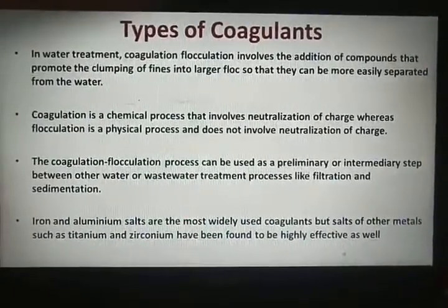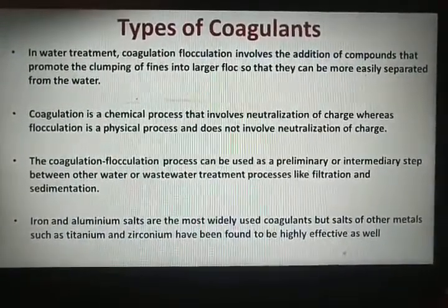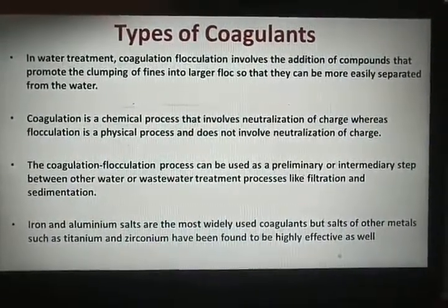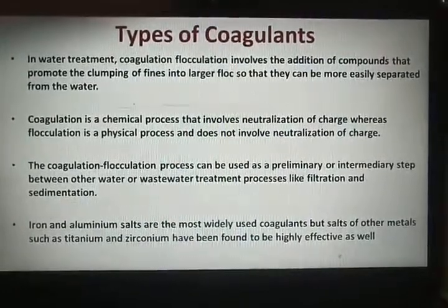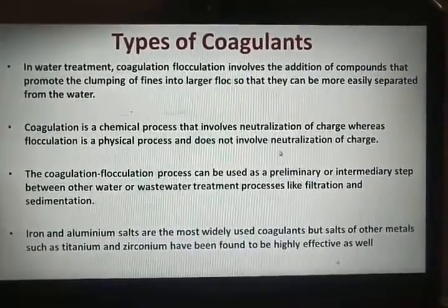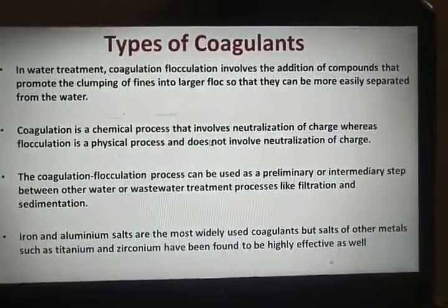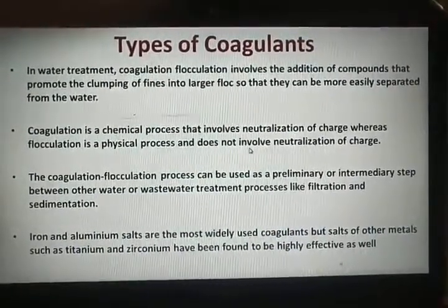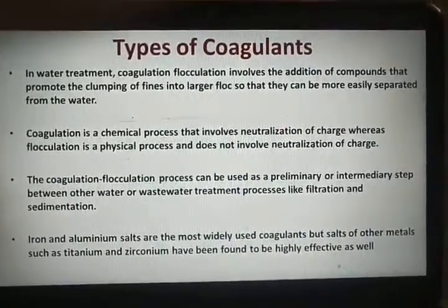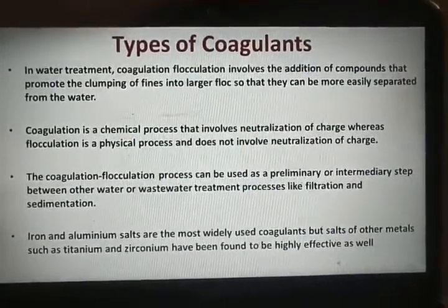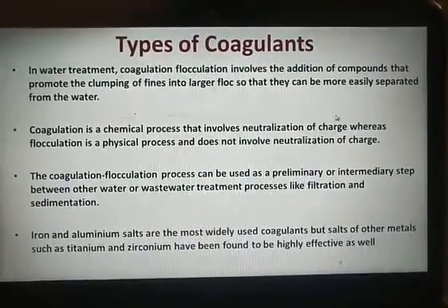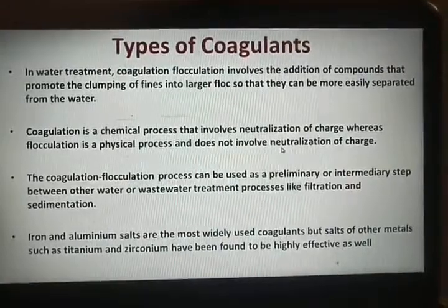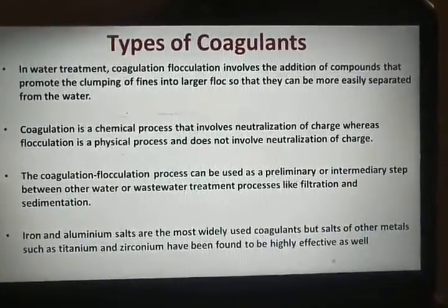Okay, so basically the particles in the water, that is colloids and suspended solids, which cause turbidity in the water, may consist of negatively charged particles, and most of the coagulants which we add to the water have positive charges, and due to that the charge neutralization process takes place in the sedimentation tank.